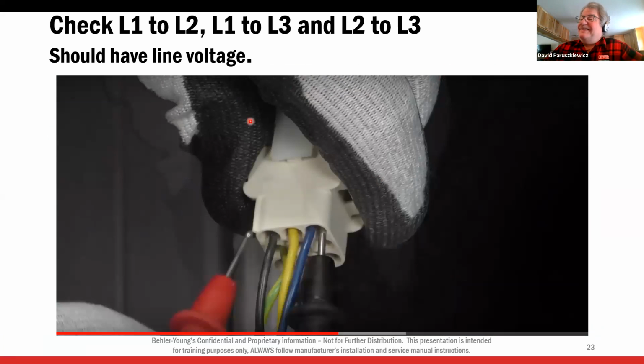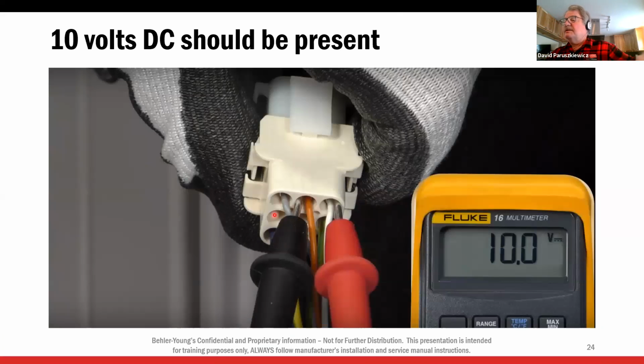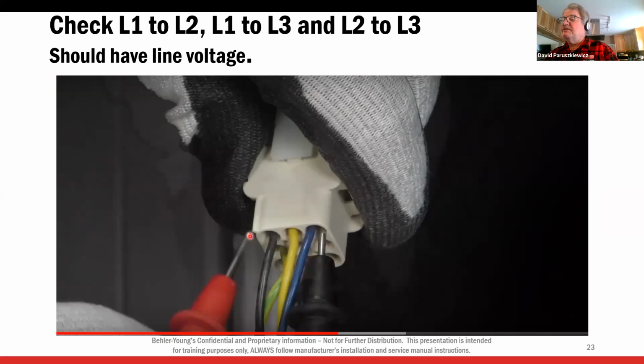All right. This is the plug. It's in line. It's in the blower compartment. So if you go into the motor, this is the best place to troubleshoot this motor. This is on the motor side. So if I follow these wires, they go right to the motor directly. Take your blower panel off. You get your meter out. You grab this plug. L1, L2, L3. So there's your line voltage, right? Take my meter. Oh, sorry. I'm going to stick my probes in there. L1 to L2, L2 to L3, L3 to L1. I'm going to check for my line voltage.